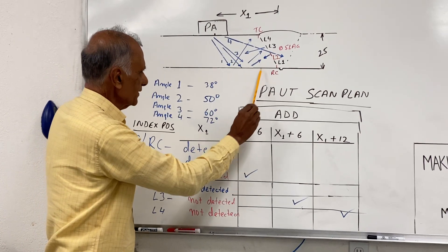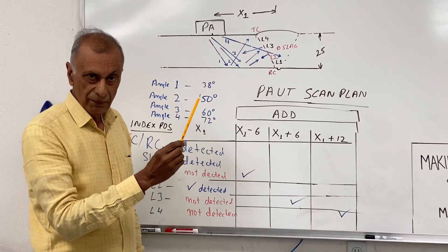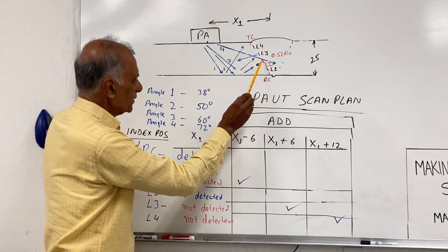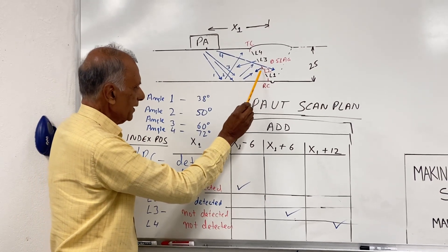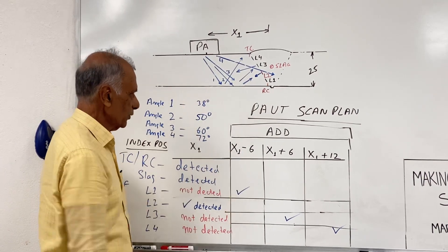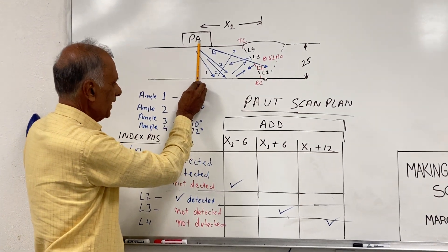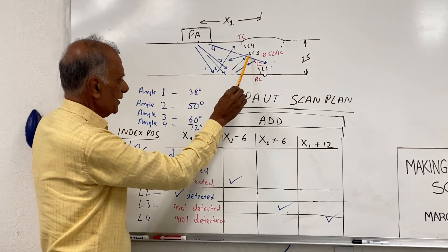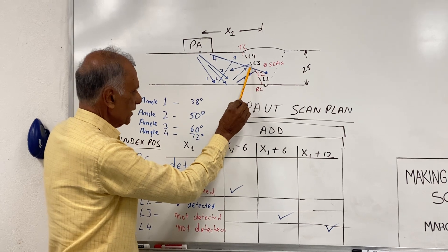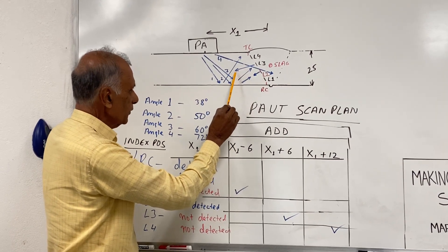Angle of incidence equals to angle of reflection. In order to see this, it has to hit at 90 degrees for the sound to be reflected back here and back to the probe. Now if I just keep the probe here and then scan it, if you look at this lack of fusion L3, the sound is going here and then it's reflecting here. The reflected sound is not going back to the probe.